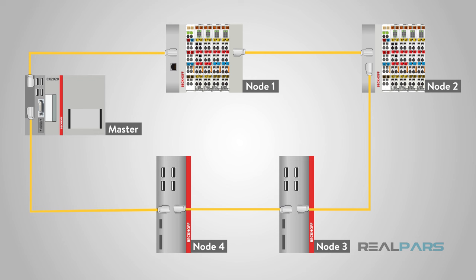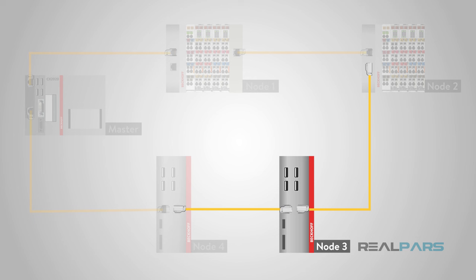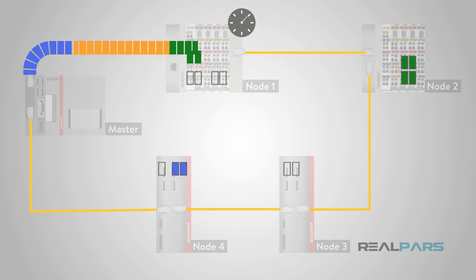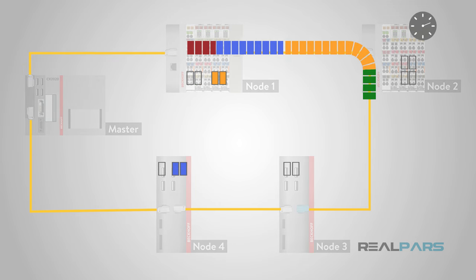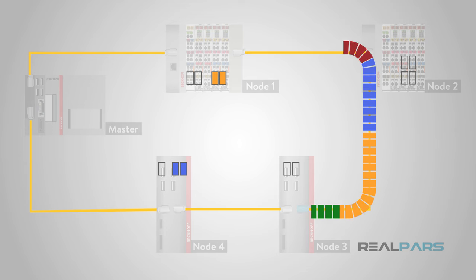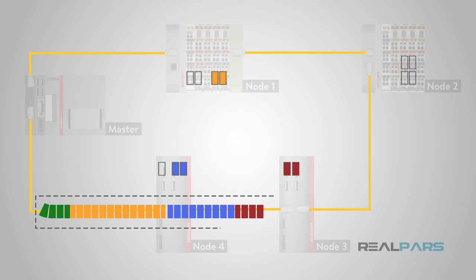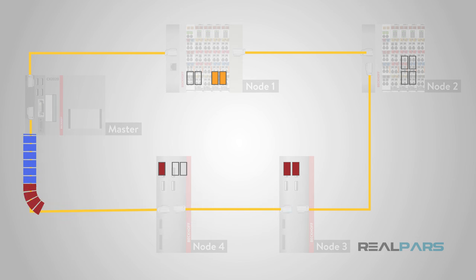EtherCAT networks do not require external switches in the network. Each EtherCAT device typically has two Ethernet ports — the first port being the receiving port or previous node's cable, and the second port connected to the next node in the network. The processing of the data on the fly in the hardware of the device is a major advantage of EtherCAT. Although there is still a small delay in the data frame as the device adds its data to it, it is greatly reduced by the often single data stream of EtherCAT versus the multiple Ethernet frames used in an Ethernet network.